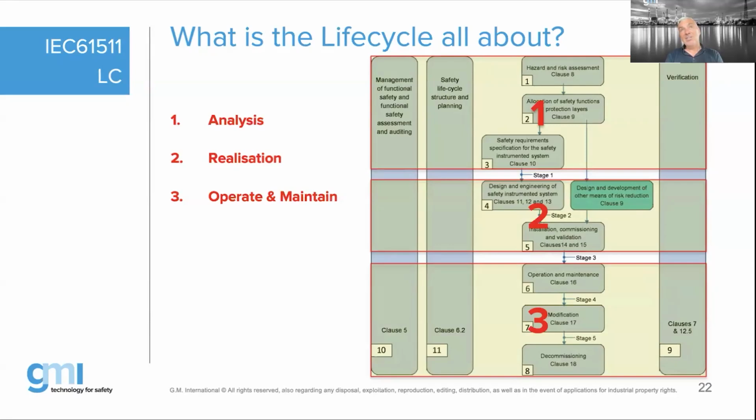Of course, if the hazard happened before and there are some historical data that you can refer to, that's sometimes what we will have to do. But if you have a new application, and today in the industry hydrogen is one example, one of the latest applications that is more and more being used, the question is, when you are designing a hydrogen plant, how do you estimate how frequent a potential hazard can happen? Do you go to other gases? Do you go to other liquids to say there is maybe a line break or something? Or where do you come up with your frequencies? That is classically what could be a challenge in your project.